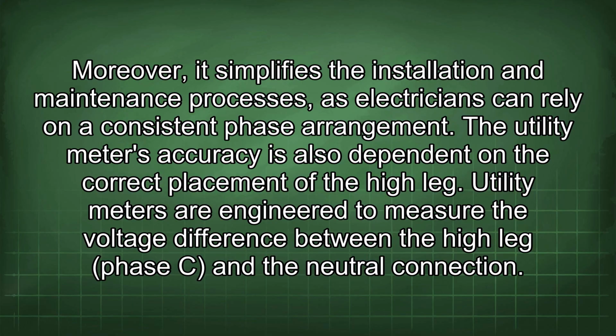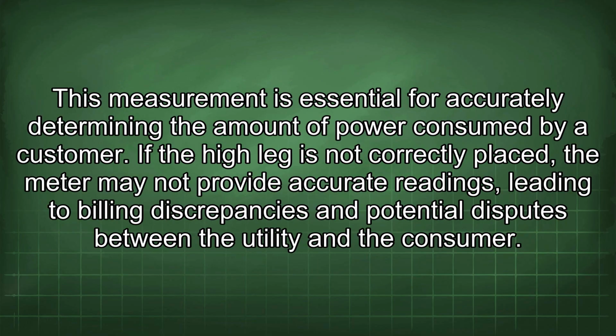The utility meter's accuracy is also dependent on the correct placement of the high leg. Utility meters are engineered to measure the voltage difference between the high leg phase C and the neutral connection. This measurement is essential for accurately determining the amount of power consumed by a customer. If the high leg is not correctly placed, the meter may not provide accurate readings, leading to billing discrepancies and potential disputes between the utility and the consumer.